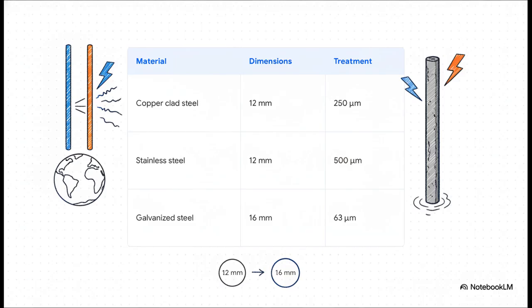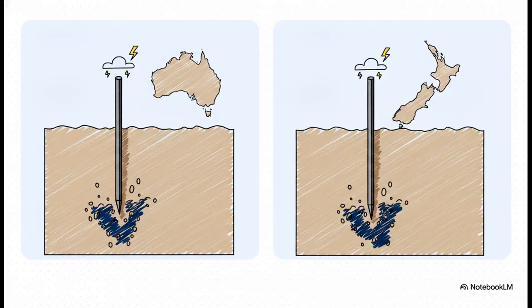This perfectly illustrates how the standard is actively accounting for different electrical conductivity and corrosion resistance over long periods of time. But hey, it's not just about what the rod is made of, it's heavily about where you put it. The standard points out a very specific geographical compliance difference here. In Australia, the vertical electrode has to be driven down to a minimum depth of 1.2 meters. But in New Zealand, it must be 1.8 meters.